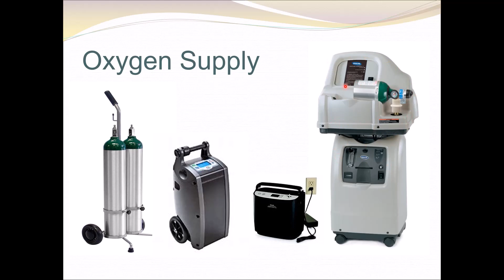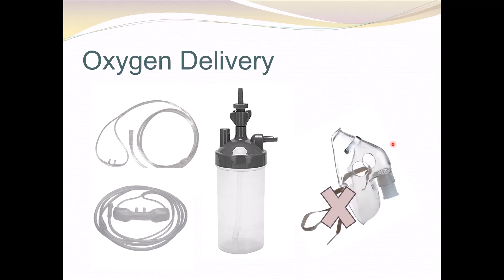With an optimizer, the same amount of oxygen can be delivered at a lower flow rate. This will allow for a single oxygen tank refill to last longer. This is a humidifier. This is a face mask. It should not be used unless one can deliver oxygen at 6 liters per minute. The usual stationary oxygen concentrator at home will deliver 5 liters per minute.